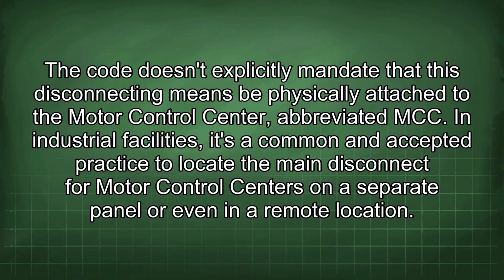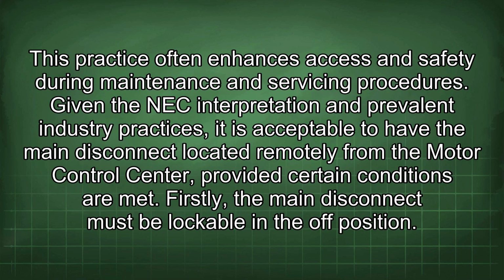In industrial facilities, it's a common and accepted practice to locate the main disconnect for motor control centers on a separate panel or even in a remote location. This practice often enhances access and safety during maintenance and servicing procedures. Given the NEC interpretation and prevalent industry practices, it is acceptable to have the main disconnect located remotely from the motor control center, provided certain conditions are met.